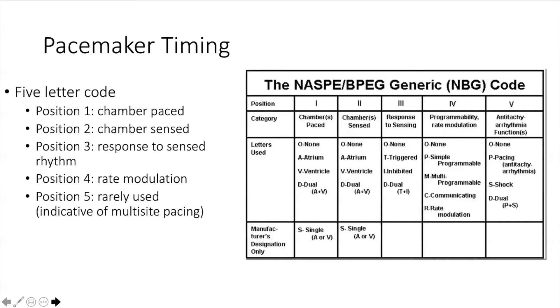I meaning that if the device senses a native impulse, it'll inhibit itself and not pulse. D meaning it will inhibit and trigger. So it will inhibit itself if it sees a native beat. However, if it doesn't, it will pace the heart. And finally, in the 4th position, you have the various programmability settings or rate modulation. This is really only used to mention rate modulation that can adjust the heart rate in response to patient activity, and this is denoted by an R. You generally don't use the other letters here. And finally, this fifth letter code is really rarely used, so I wouldn't worry about it.